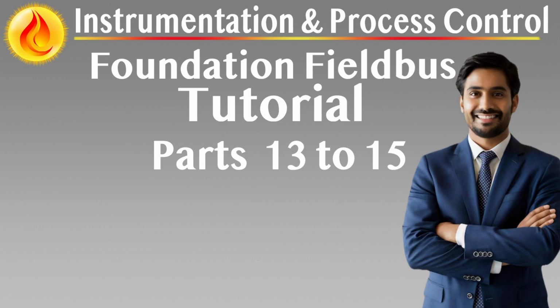This phase must be executed with a high degree of precision and adherence to Fieldbus-specific standards to preserve signal integrity, ensure device functionality, and maintain the deterministic communication required for distributed control. Foundation Fieldbus installations differ significantly from conventional analog wiring, particularly in aspects such as shared bus segments, power conditioning, and signal shielding. The first step in the installation phase is the preparation and verification of installation materials.